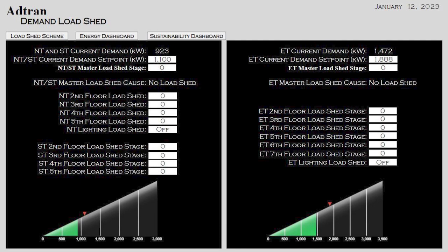And we had it, you can see where it says no load shed. That's if it was at stage 0. If he overrode that point, the master load shed, then that master load shed cause would show manual override, or it would show, I think just demand load shed of, it was looking at that set point and it needed to go into it automatically, so it did. So those were the key components of that dashboard.